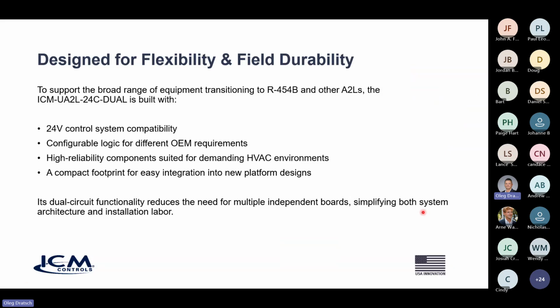So again, the flexibility of this product, really, it's a universal board. It's designed to work with basically any system out there. The logic on it can be configured for different OEM requirements, and it really uses that 24-volt control system, or that control source, to really perform the mitigation actions. Compact footprint, so it comes with a cover, can be installed close to the evaporator coil, and that's where you want the sensor placed. So it's really just a little kit that installs and meets code compliance for A2L safety and mitigation.